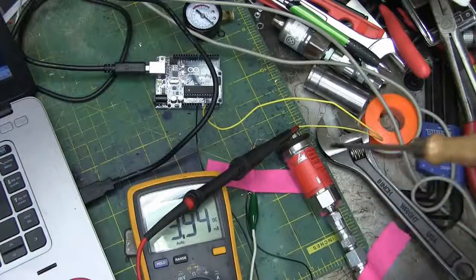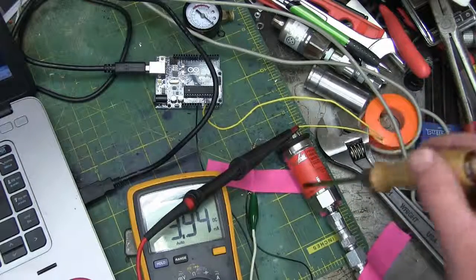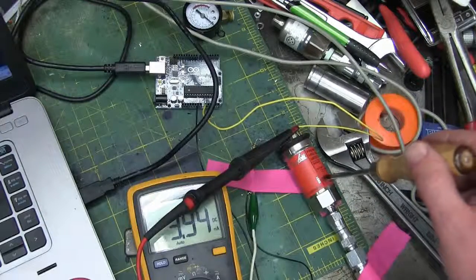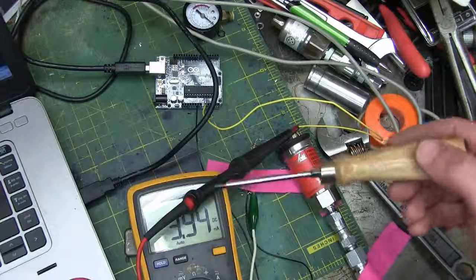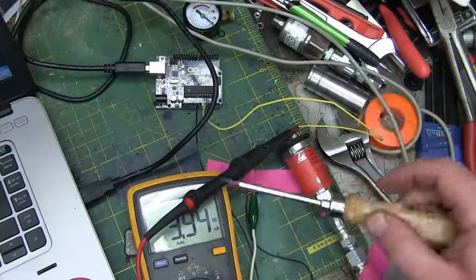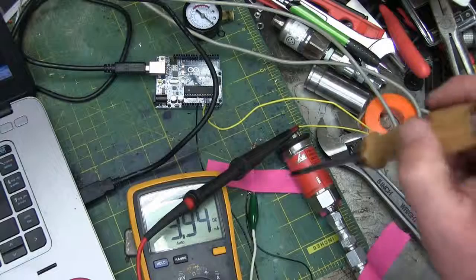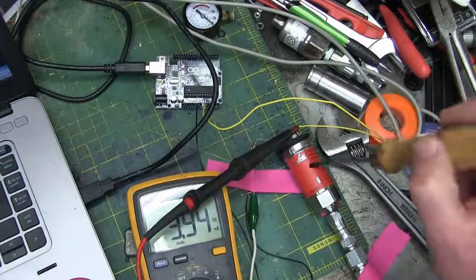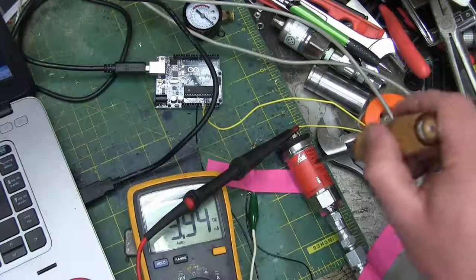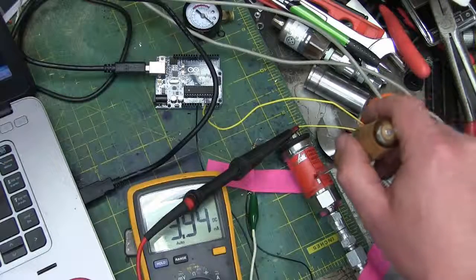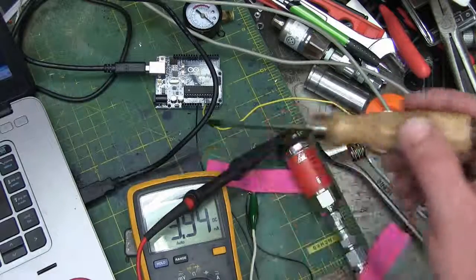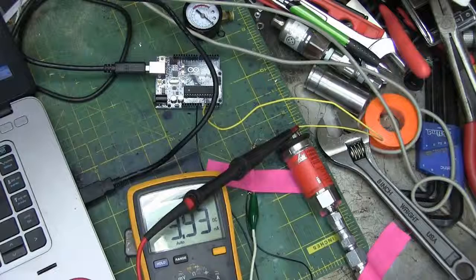Now we're running into a bit of a problem because of the non-linearity of this sensor at the bottom of the scale, near 0 psi. So what I've done is measure with my nice big, accurate gauge what the pressure in the tank is right now, 66 psi. We're going to apply that to the sensor and see what we get on the serial monitor.